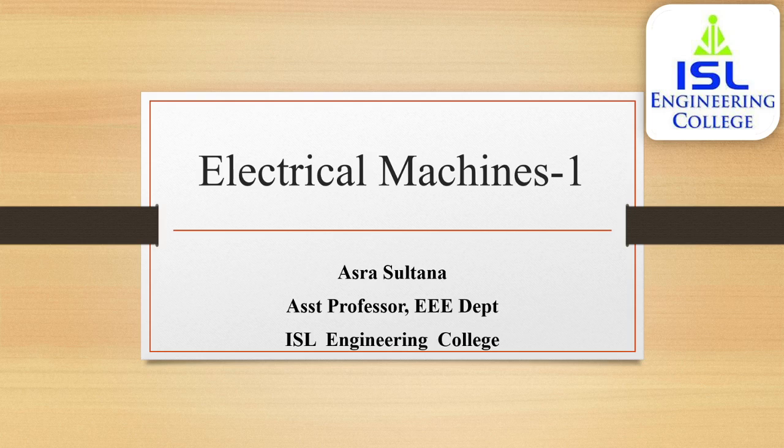And what are the problems of armature reaction? There are two problems associated with armature reaction. First, armature reaction will decrease the main flux by some amount, like 10%, and this will cause the generated EMF in the generator to fall with the increase in the load current. Second, brushes will be shifted from their neutral zone. That is, there will be distortion of flux and the neutral zone will be shifted. To ensure good commutation, brushes must be placed in the neutral zone. But because of the distortion of the flux, the neutral zone will be shifted. And if the load varies frequently, shifting the brush position will not be practical.